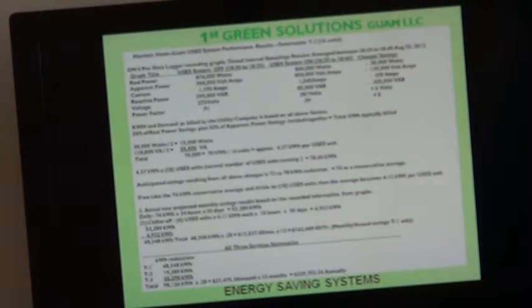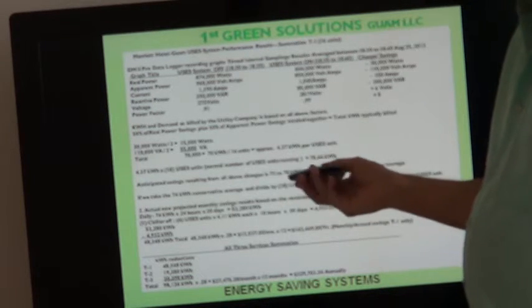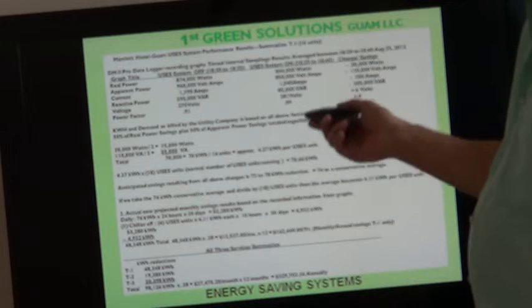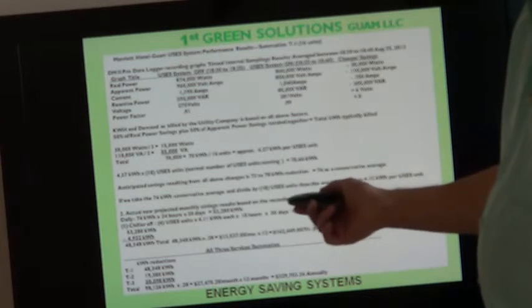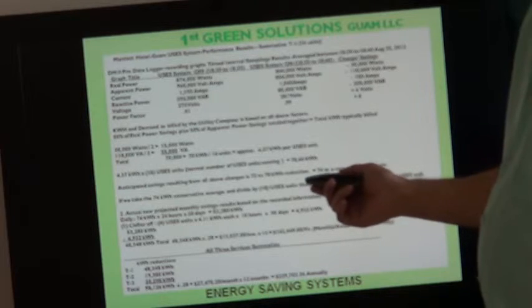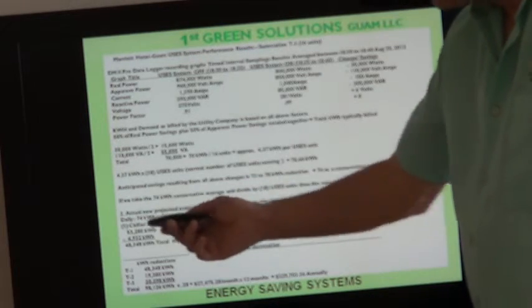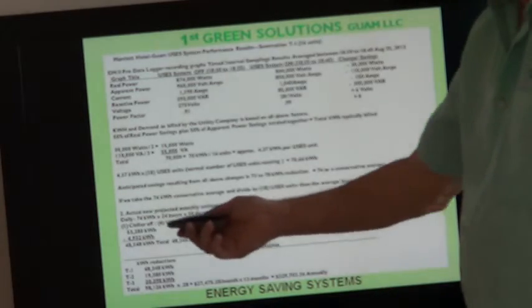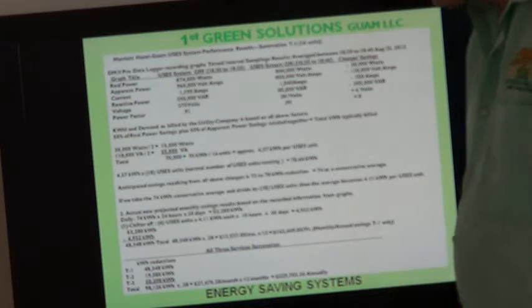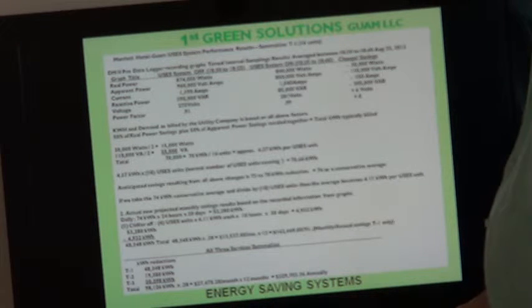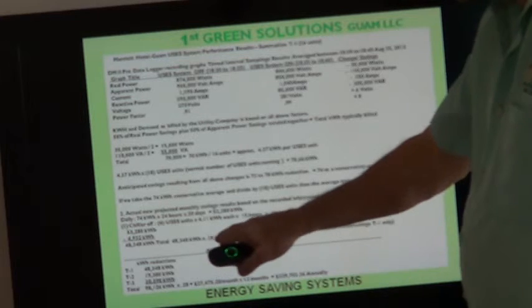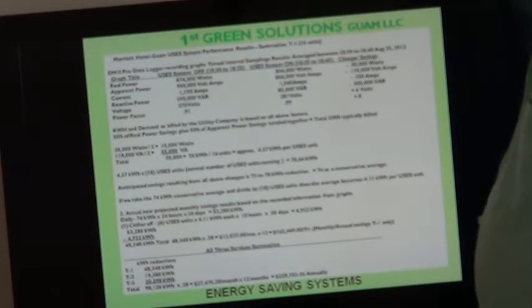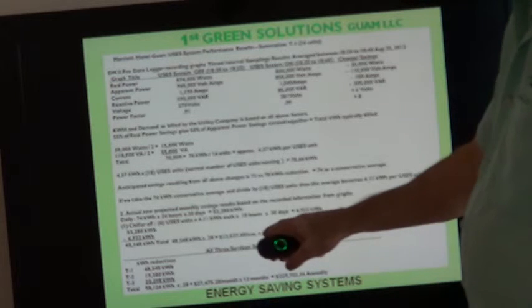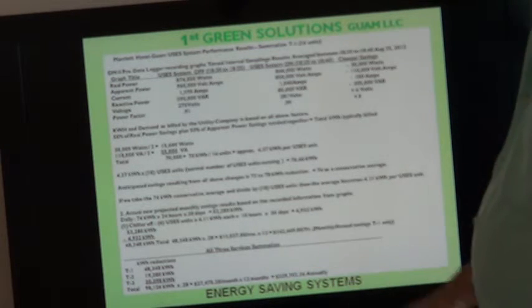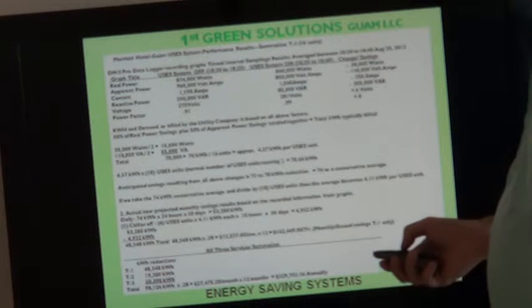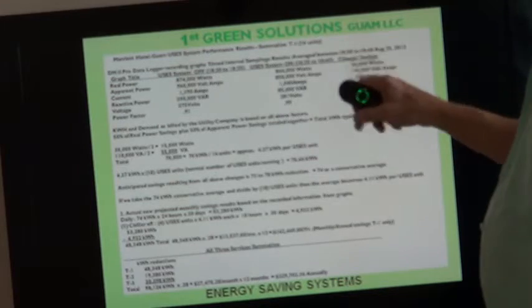for the 16 units. Doing all the math for the various amounts of reduction that's happening from each unit, by adding 2 more units, because we had an additional amount of kVAR that we could capture, and by subtracting the chiller that is turned off at night, we end up coming up with 48,000 kWh saved per month at 28 cents a kilowatt hour. This equals $13,537 times 12 months of the year, which ends up being $162,000 for that particular service. They have 3 services.